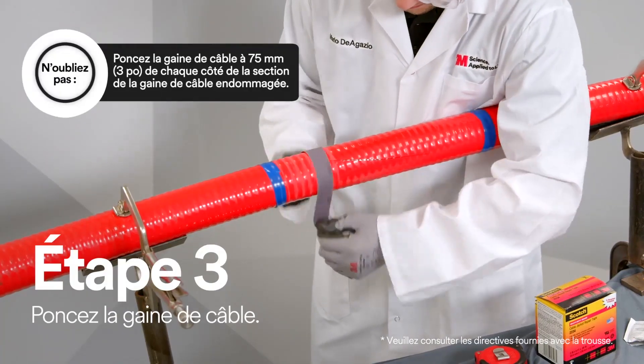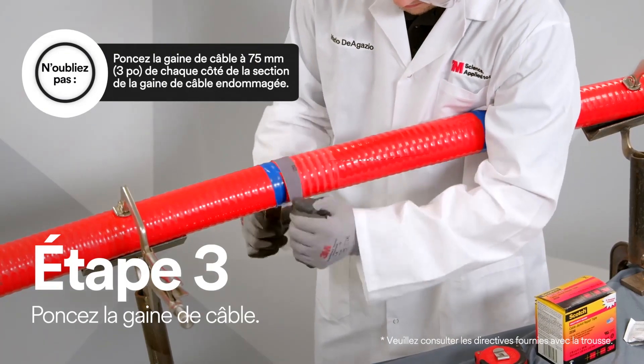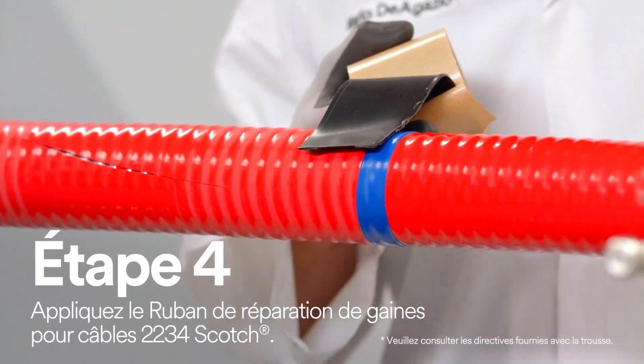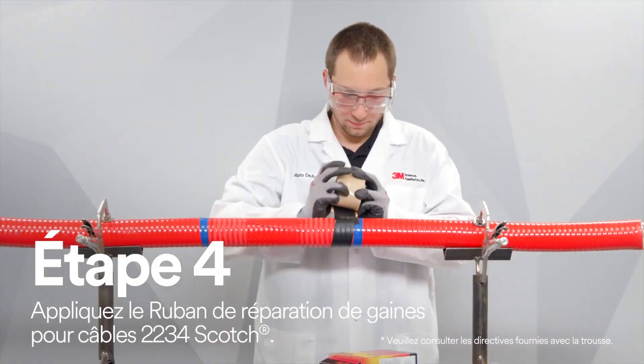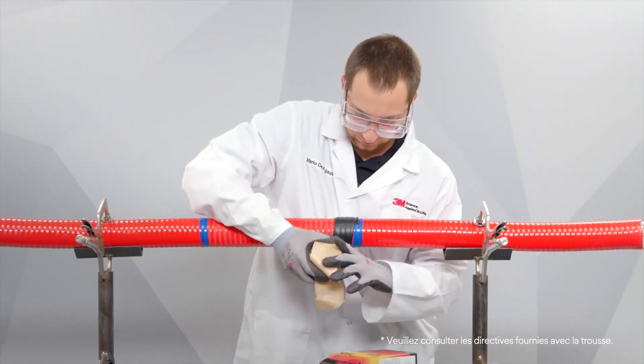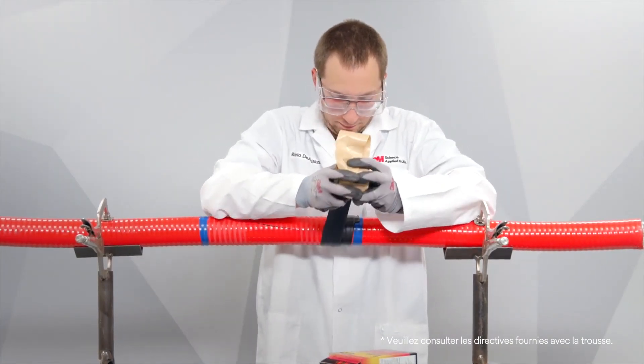Abrading the cable is important because it helps improve adhesion. Now you need to wrap one half-lapped layer of Scotch Cable Jacket Repair Tape 2234, extending at least two inches on each side beyond the damaged cable jacket.